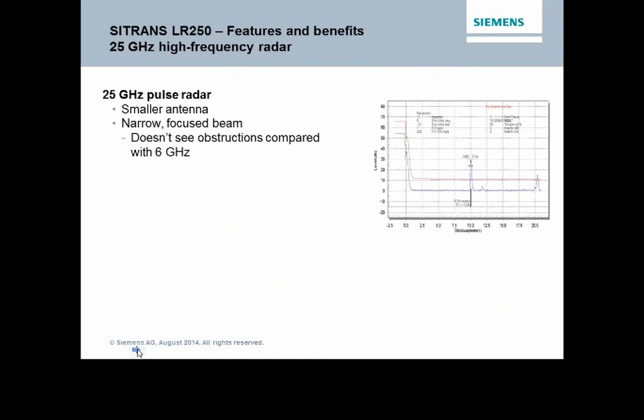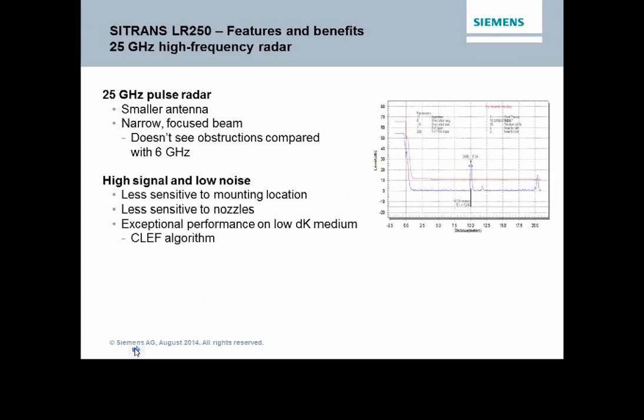Some of the features and benefits we'll get into briefly here. We're looking at a 25 gigahertz pulse radar. A lot of what was on the market earlier was 6 gigahertz. So where there would be a lot of noise, we can get a very strong signal. This is a liquid application. What we see here is a normal echo profile, and then our dynamic TVT. This would be an ideal application for a measurement. We can see not only the distance in this application, but also where the noise is, and evaluate the echo profile and optimize our parameters until we've optimized our profile. With a 25 gigahertz radar, we no longer have the issues that plague the low frequency units with noise.